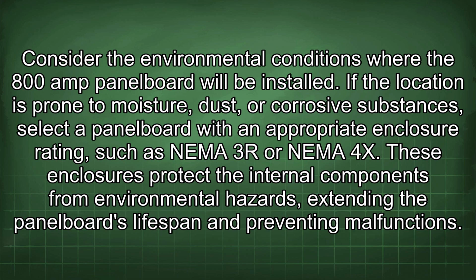Consider the environmental conditions where the 800 amp panel board will be installed. If the location is prone to moisture, dust, or corrosive substances, select a panel board with an appropriate enclosure rating, such as NEMA 3R or NEMA 4X. These enclosures protect the internal components from environmental hazards, extending the panel board's lifespan and preventing malfunctions.